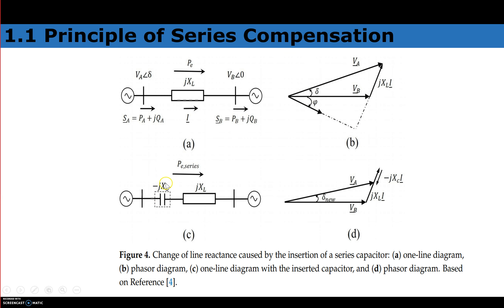When a series compensator is used, a capacitor XC is connected in series with the inductive reactance XL, giving a net reactance of XL minus XC. This compensates for XL, reducing the voltage drop. On the phasor diagram, the voltage drop comes down by the capacitive reactance XC amount, and as a result the sending end voltage point shifts, reducing the angle delta.